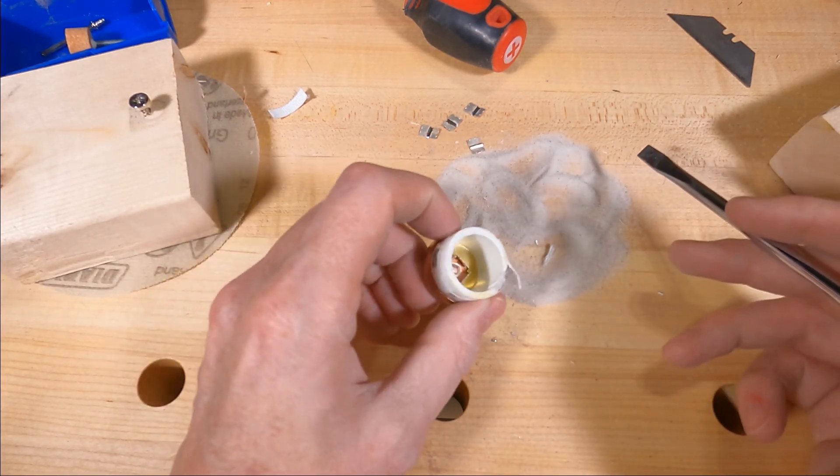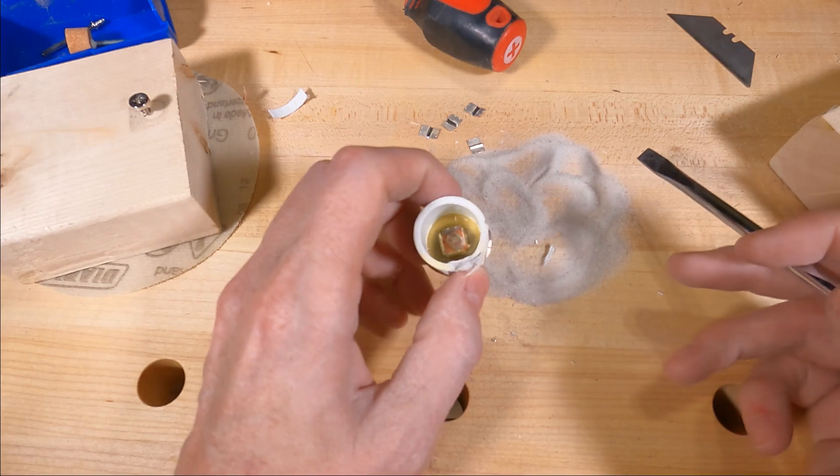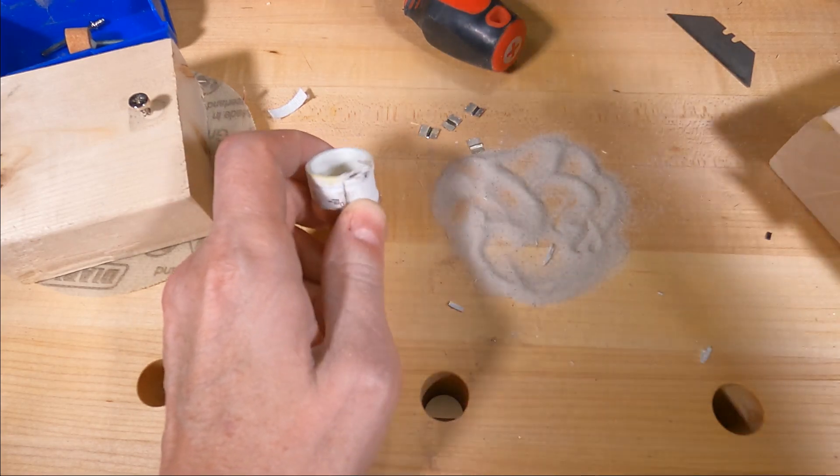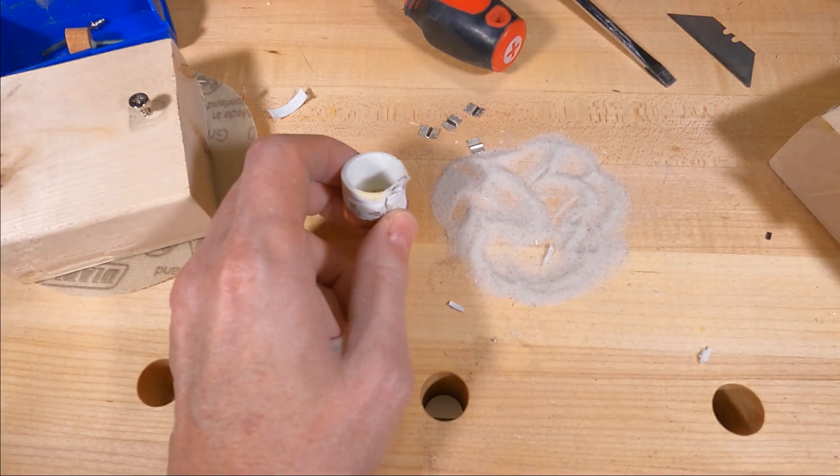Anyway, there you go. That's what's inside of a blown T-class fuse, and that's the silica sand that quenches the arc. Cheers.